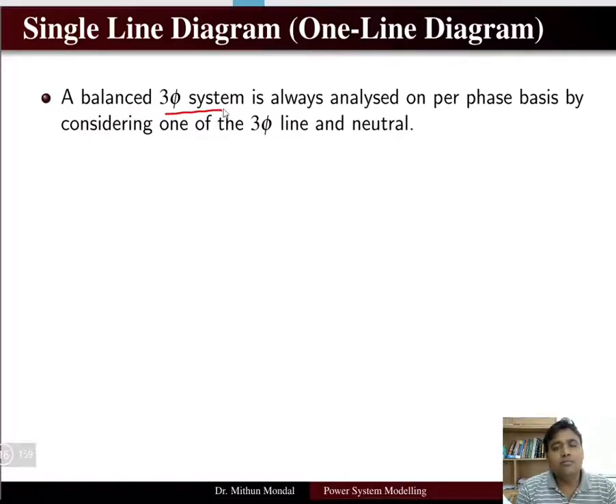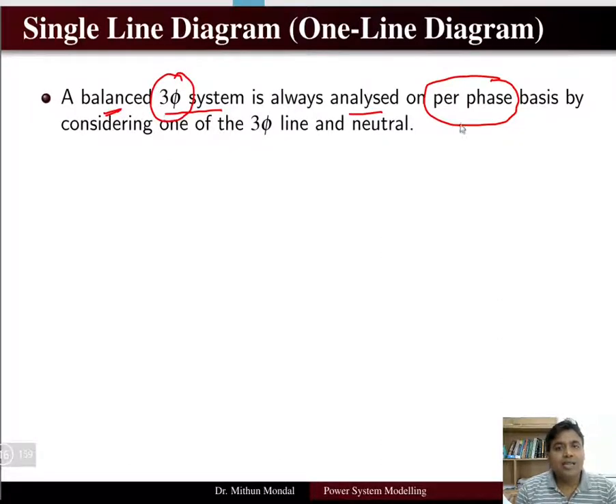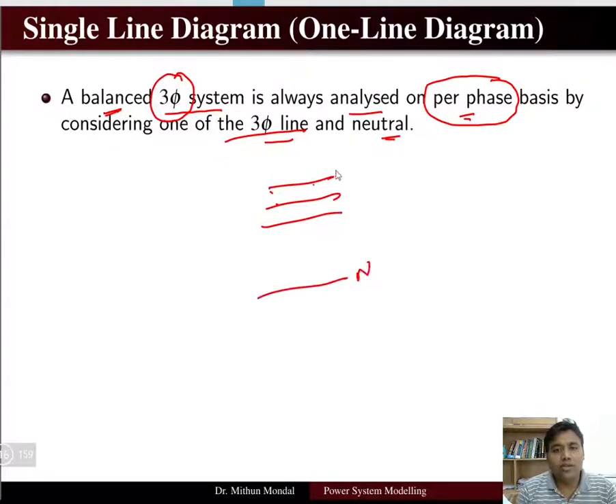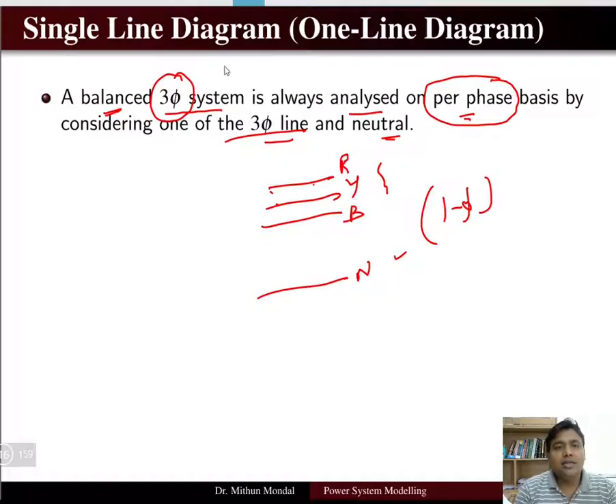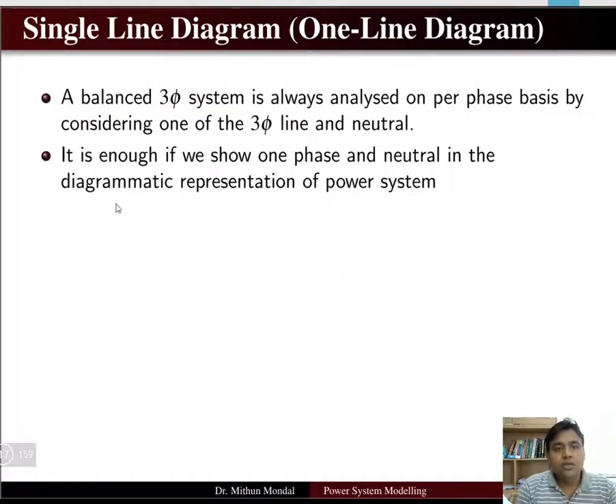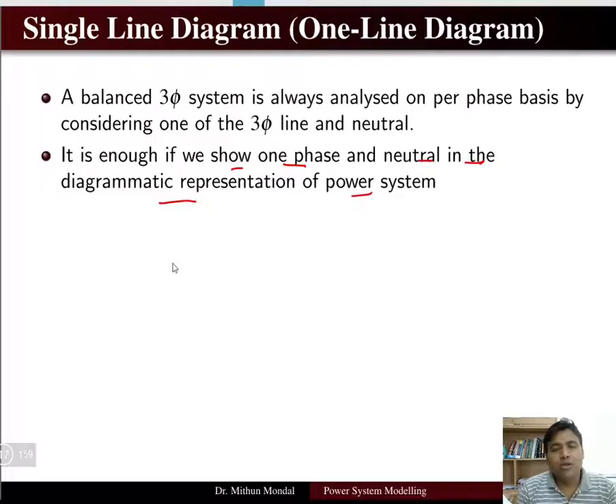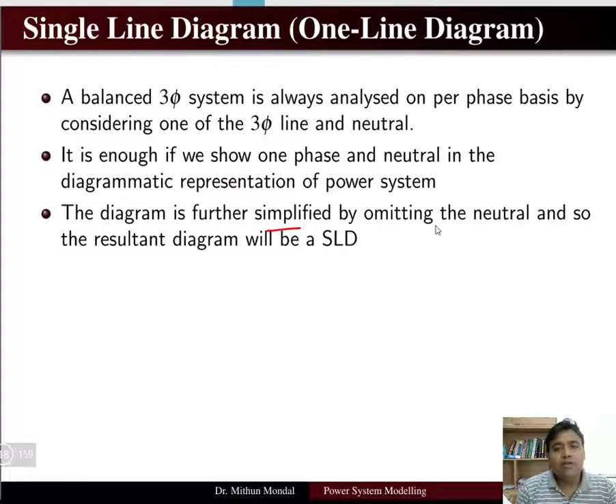A single line diagram represents a balanced three-phase system analyzed on a per-phase basis. In a three-phase system that is balanced, we can analyze on a per-phase basis by considering any one of the three-phase lines and the neutral. You can take any one line and the neutral to form a single-phase circuit. All single line diagrams are represented on a per-phase basis, so it is enough to show one phase and neutral.